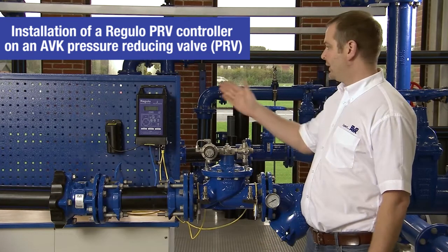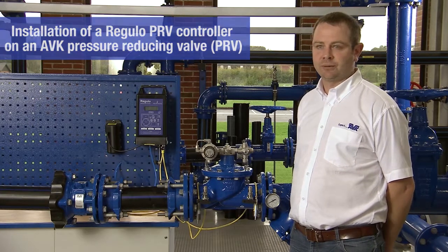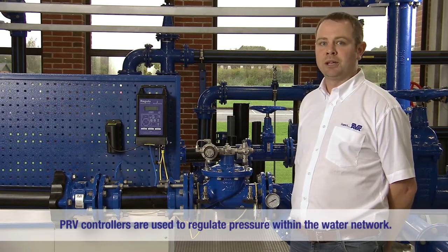Today I'm going to talk to you about the installation of a Regulo PRV controller on an AVK series 859 pressure reducing valve. PRV controllers are used to regulate pressure with flow within the water network.